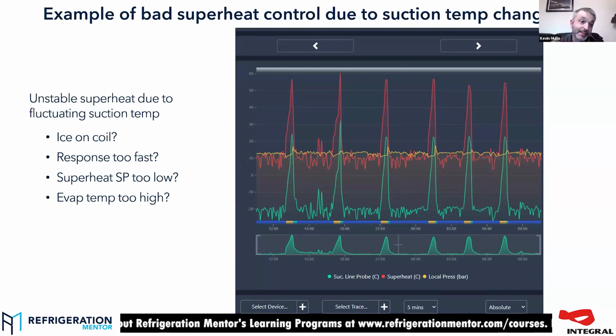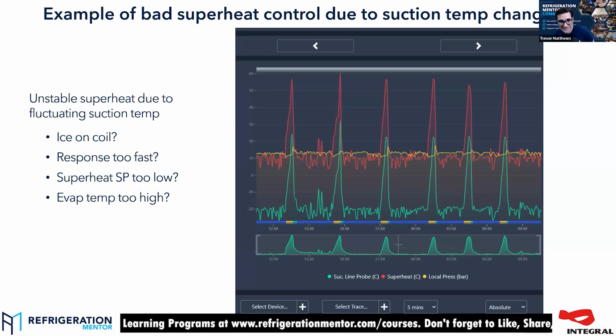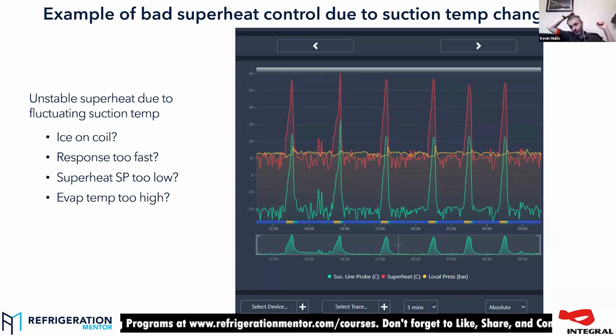Yeah, and actually, it's something that's relevant to this. It doesn't even have to be a solid block of ice. What you get, especially on cold stores, you see a lot on CO₂ for some reason. I don't know why, answers on a postcard, but you can get a ribbon of ice, let's say on the fan side of the coil. If your coil's in a Costco, let's say, and it's 20 feet in the air, and the fan's spinning, if you've got a ribbon of ice this high on the front of the coil, you're probably not going to see it from the ground.